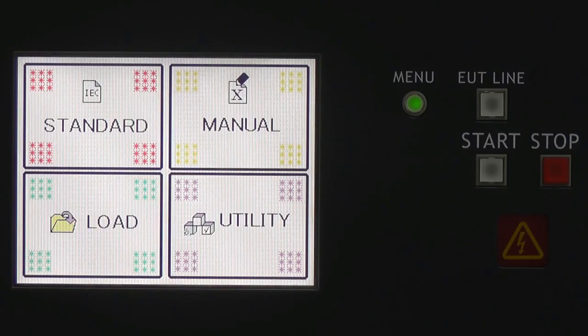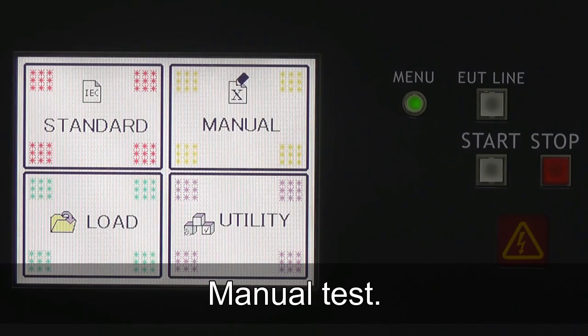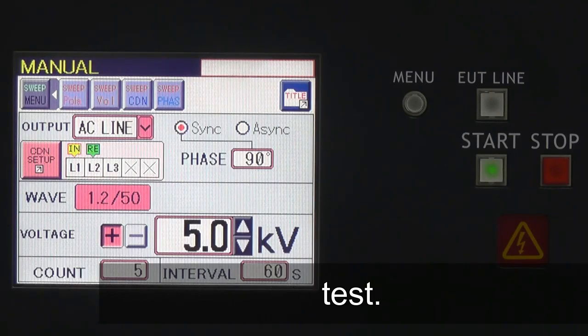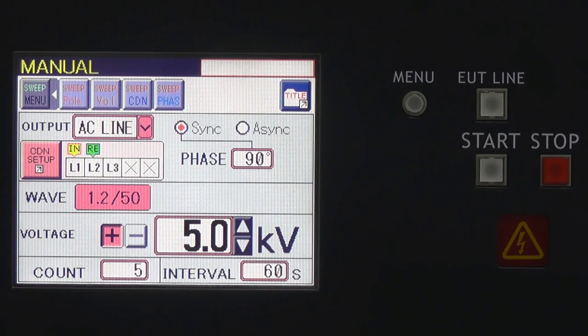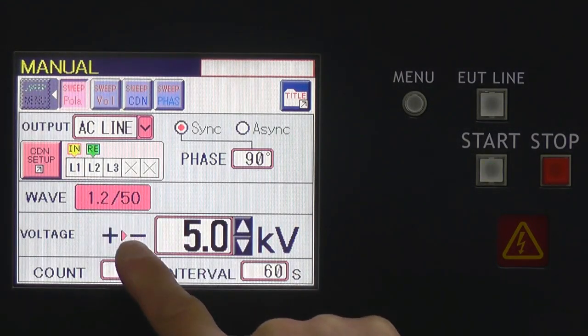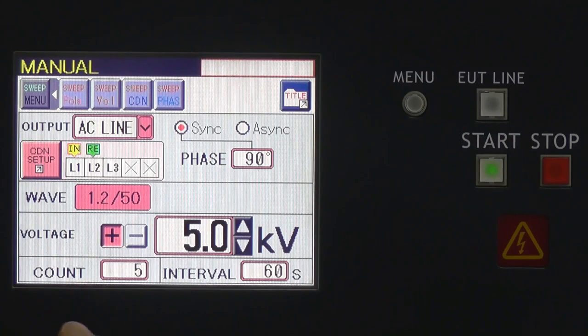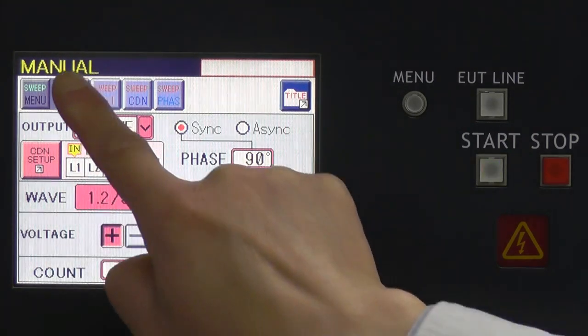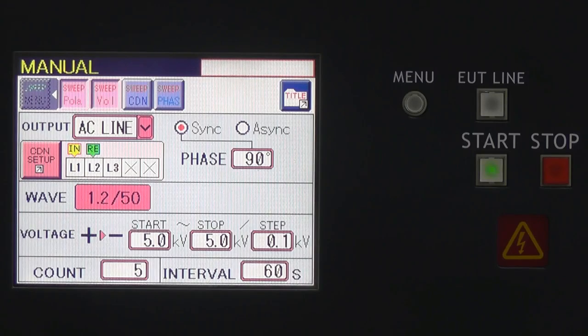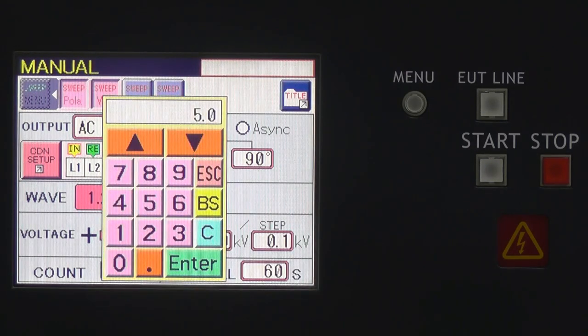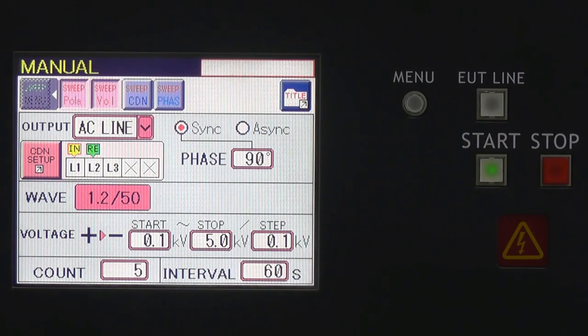Okay, let's take a look at the manual test. In the manual test, you can set the sweep functions of the polarity, surge voltage, serial outputs, and phase angles. For example, if you want to sweep the polarity, I press here, and the test will automatically run from plus to minus. Okay. Then the next step, voltage. Set the voltage here. Let's say we want to start from 0.1 kV to 5 kV at 0.1 kV per step.